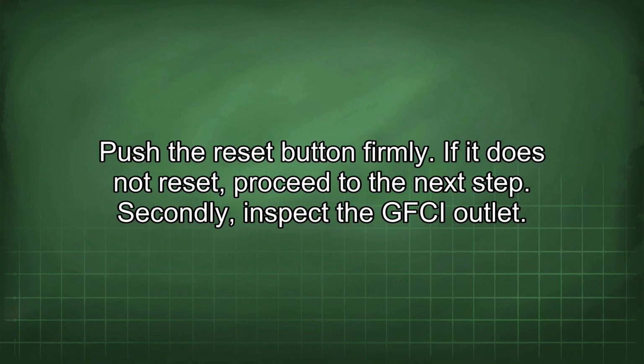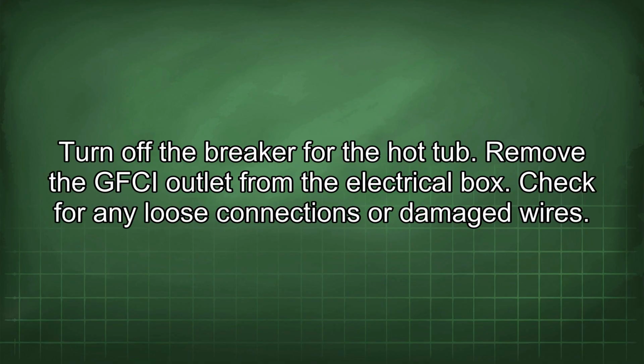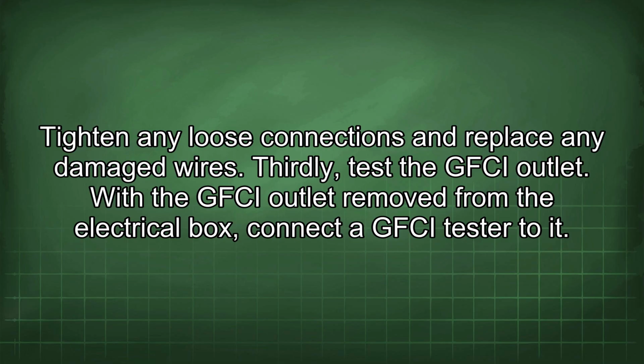Secondly, inspect the GFCI outlet. Turn off the breaker for the hot tub. Remove the GFCI outlet from the electrical box. Check for any loose connections or damaged wires. Tighten any loose connections and replace any damaged wires.